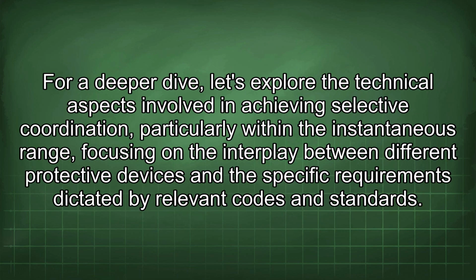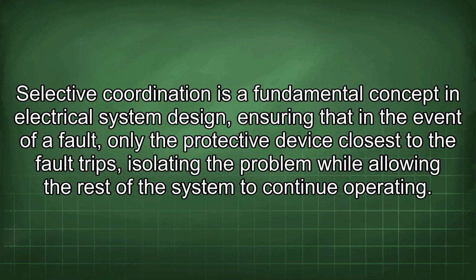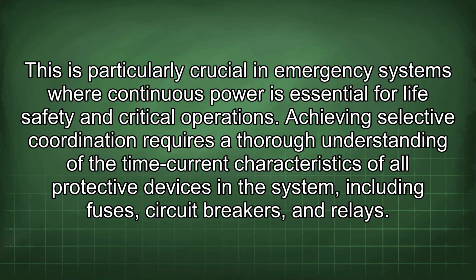For a deeper dive, let's explore the technical aspects involved in achieving selective coordination, particularly within the instantaneous range, focusing on the interplay between different protective devices and the specific requirements dictated by relevant codes and standards. Selective coordination is a fundamental concept in electrical system design, ensuring that in the event of a fault, only the protective device closest to the fault trips, isolating the problem while allowing the rest of the system to continue operating. This is particularly crucial in emergency systems where continuous power is essential for life safety and critical operations.